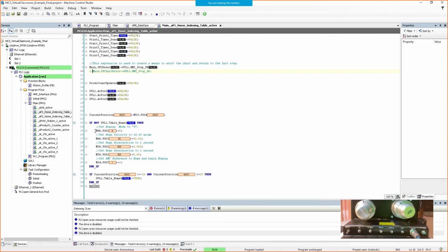So what you'll find out is menu 40 in the drive is everything to do with homing. So I'm using home mode 8, which just says home to a sensor. All right, that's a whole separate conversation, but homing to a sensor, I set my speed in menu 40 in user units, UUs per millisecond are the terms being used.